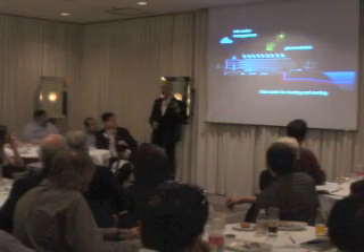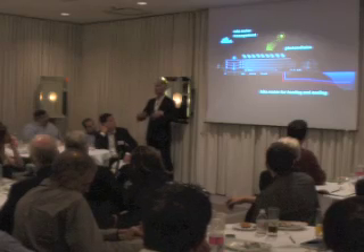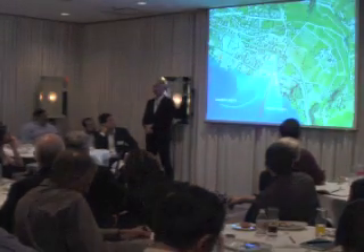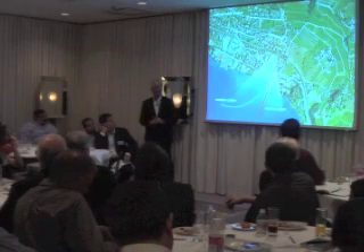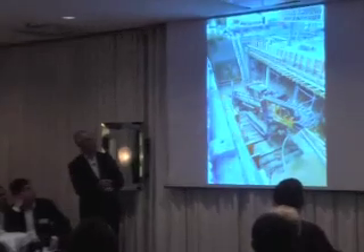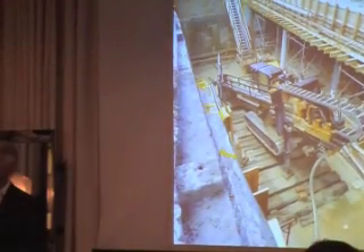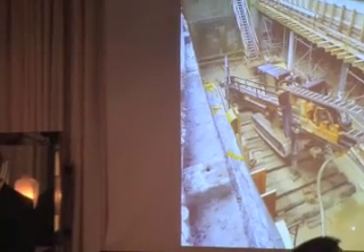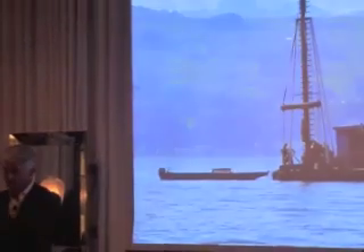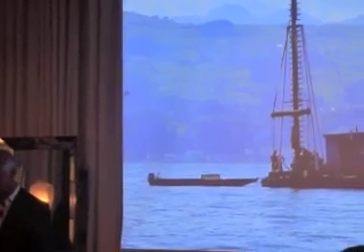The gate itself is all about the roof design. The roof protects against aggressive winds and at the same time provides energy, as we are putting in photovoltaic and solar — purely carbon free. We used the whole roof as a photovoltaic power station, generating more electrical power than the building uses for most of the year. We also draw lake water from Lake Zurich — a suction pipe and a return pipe, with cold water coming in and relatively warmer water going out. The pipe was drilled nearly horizontally, sloping into the lake about 150 meters, through underground since surface digging was not permitted, ending 70 meters from the shore. This provides the main energy for heating and cooling.